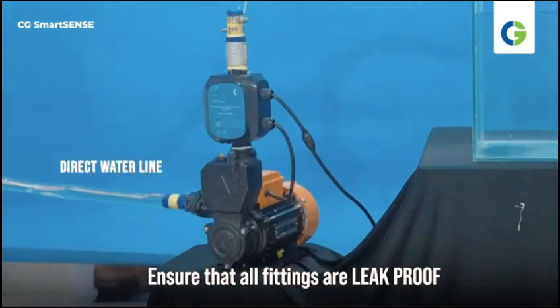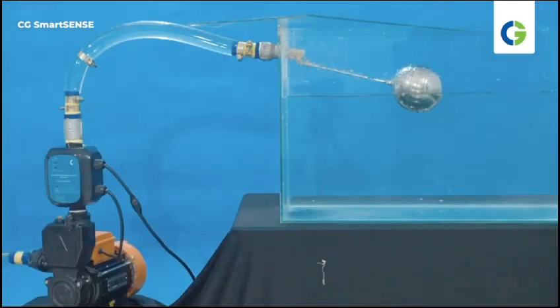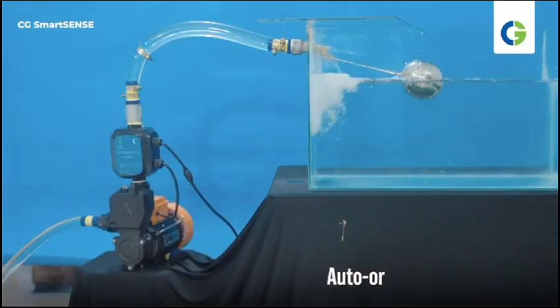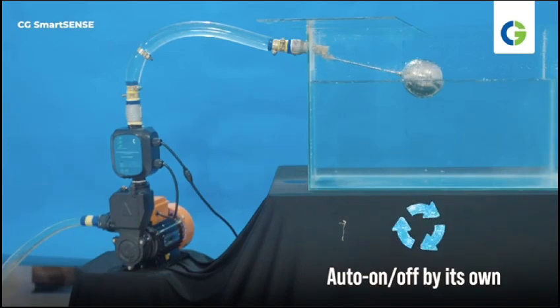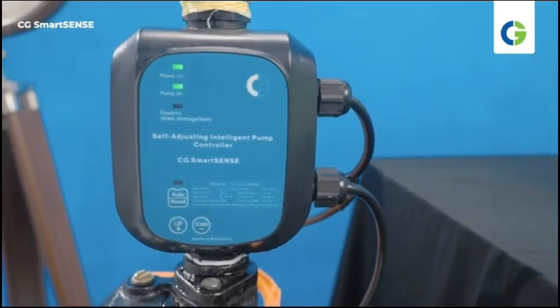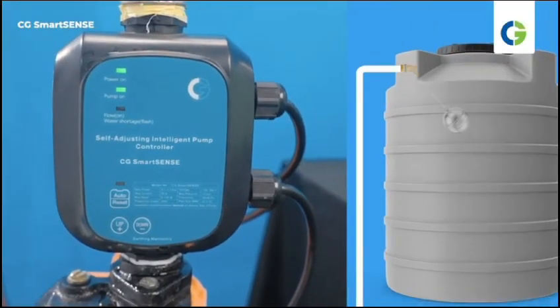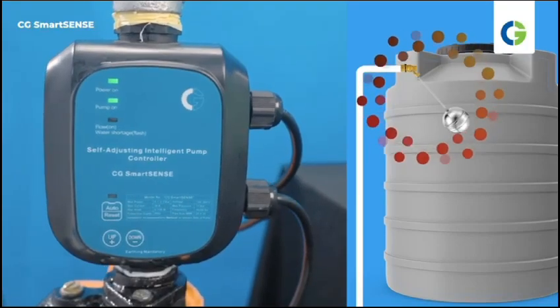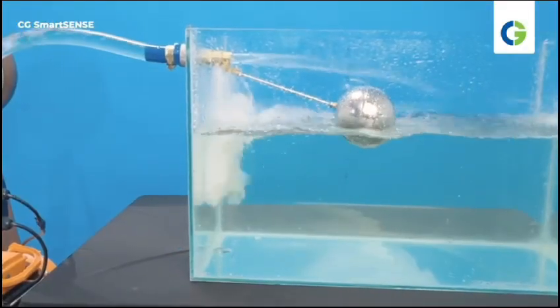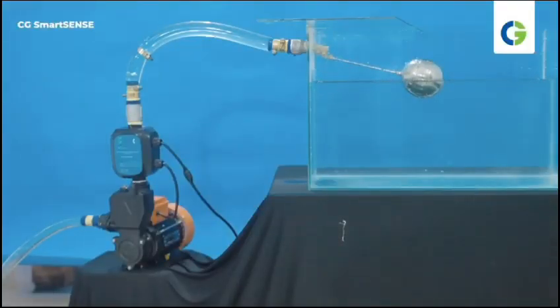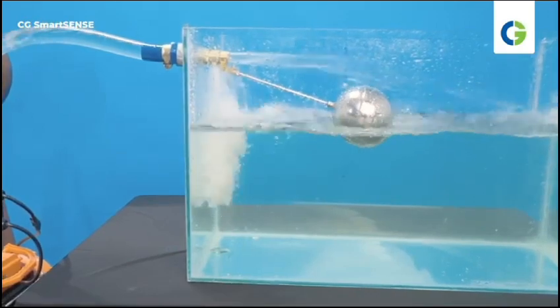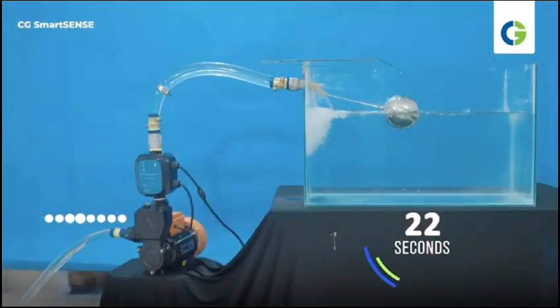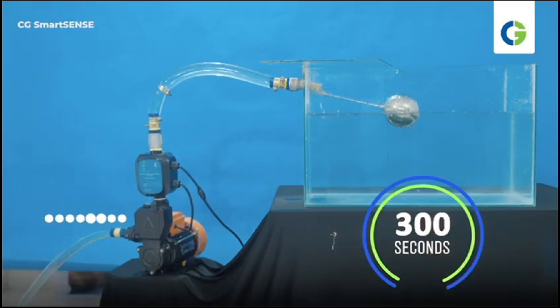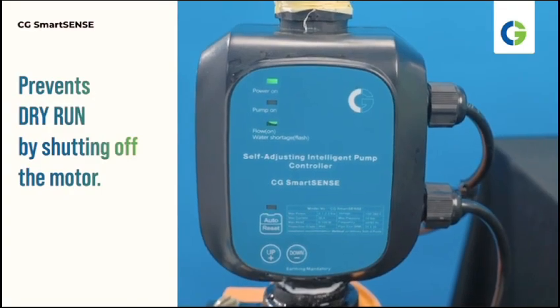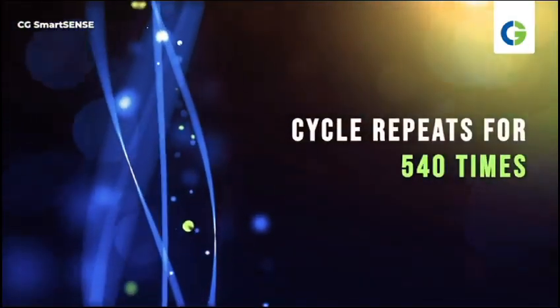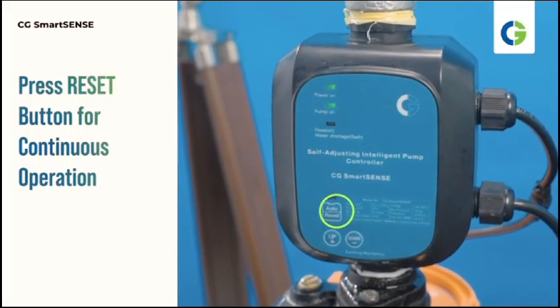Application 1. Connect the suction pipe to the direct line, and then the delivery pipe to the controller outlet to the overhead tank. In this case, the pump will work automatically without anybody's interventions for start and stop operations. Our cordless smart controller detects water from the direct line and also checks the water availability in the overhead tank before switching on the pump. If no water is in the overhead tank, then the pump will start automatically. When the water level drops in the overhead tank, the pump will resume its actions and fill the tank again by its own. If no water is at the suction pipe, then our pump will keep detecting the water for 300 seconds. Then it will turn off the motor operation to protect it from dry run. This cycle repeats for 540 times. After that, we need to press the reset button for continuous operation.